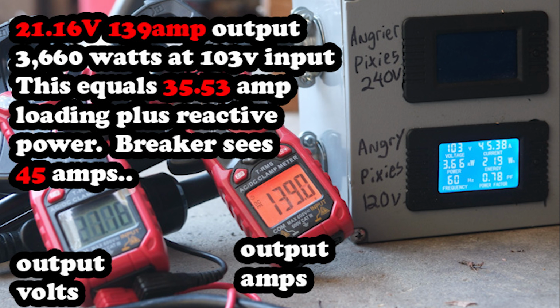Again, generators are designed a lot different with breakers because there isn't enough power to allow overloads like this. Therefore, they're a little bit more cautious, because that's exactly how you end up burning internal wires and stuff on circuitry, putting that kind of a load on it. Now, its power factor's at 0.78, 0.80. It bounced between there, which isn't that bad.